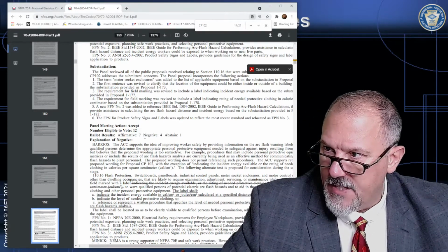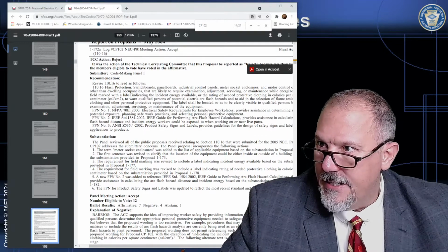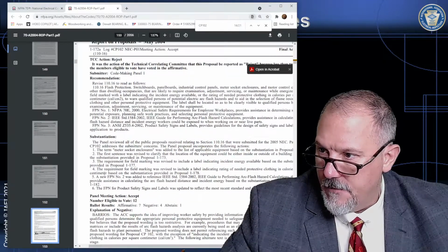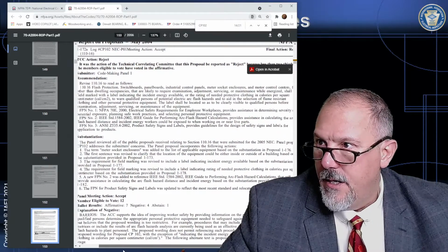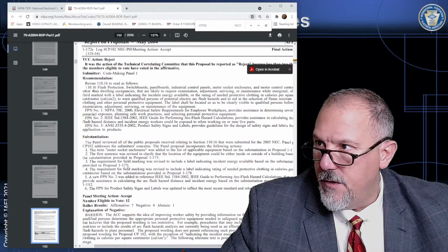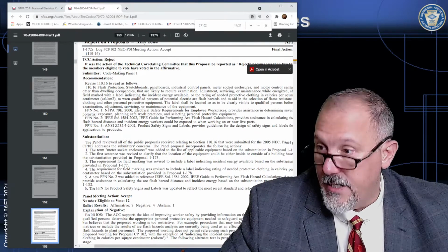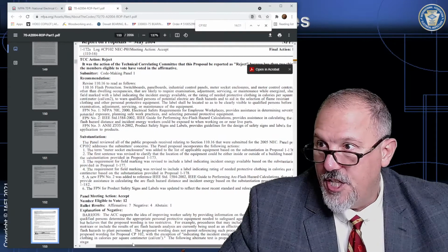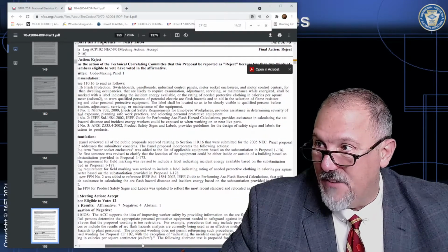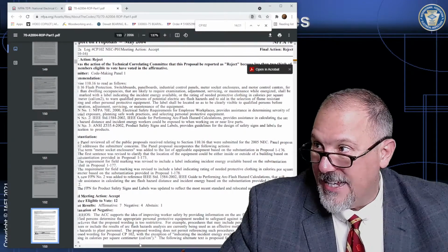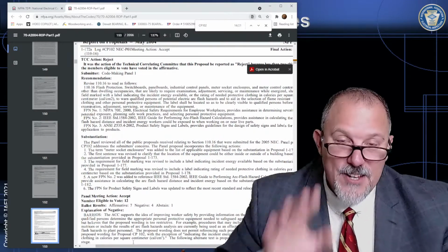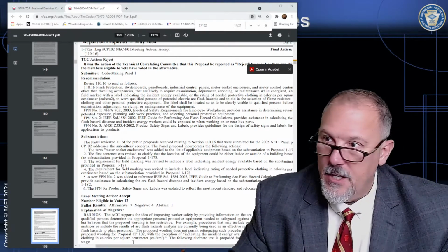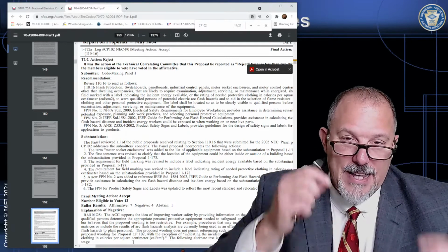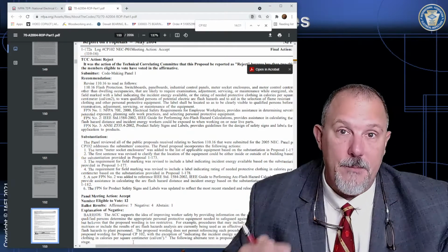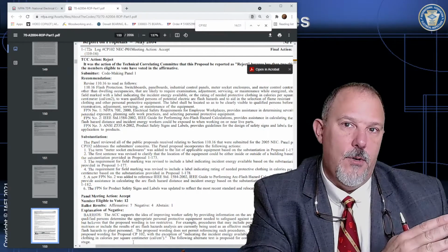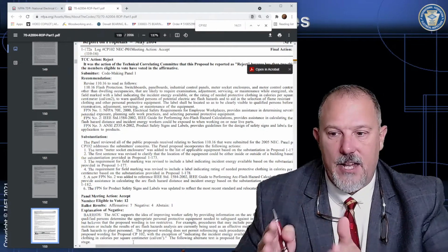So this was an accept, affirmative 7, 4 negatives, and we're going to look at what they did. Substantiation. Arc flash, switchboards, panelboards, enclosures, motor control centers, other require examination. That all seems the same. Oh, look at this. Calories per centimeter squared. Shall be field marked with a label indicating the incident energy available or the rating of needed protective clothing in calories per square centimeter, to warn qualified persons. So look, it's cropping up again to require calories per centimeter squared, not just a generic label. So you see the intent from the get-go was to create a label that says calories per centimeter squared.